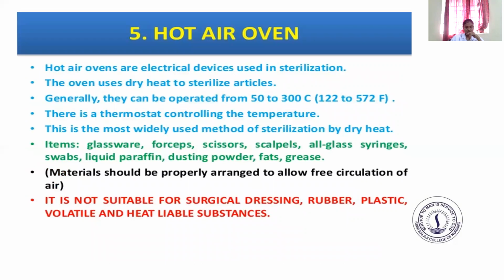And then hot air oven. Hot air ovens are electrical devices used in sterilization. The oven uses dry heat to sterilize articles. Generally, they can be operated from 50 to 300 degrees centigrade. It means 122 to 572 degrees Fahrenheit. There is a thermostat controlling the temperature.